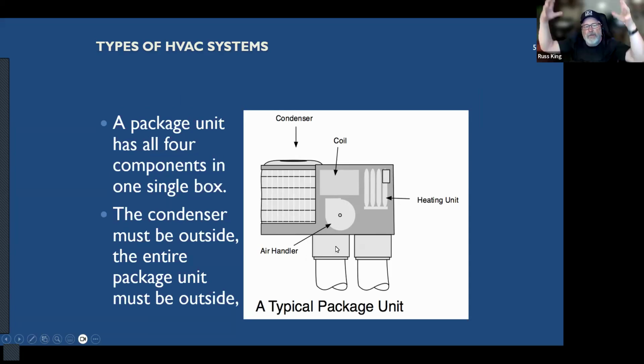And these package units can be sitting up on the roof of the house. If you drive down 99 in the Central Valley and look off into those neighborhoods, you'll see millions of package units up on people's roofs. They're these big greenish gray boxes that sit up on the roof. That's their HVAC system, all in one box. They can also sit on the ground next to the house if it's a raised floor house, and the ducts can go into the crawl space, or it can sit up on the roof and the ducts all go down into the attic. So that's a package unit.